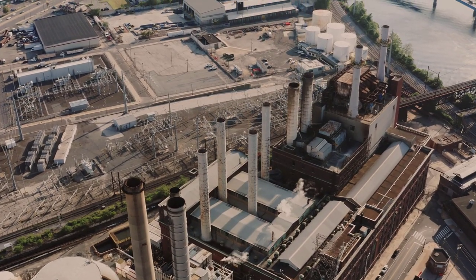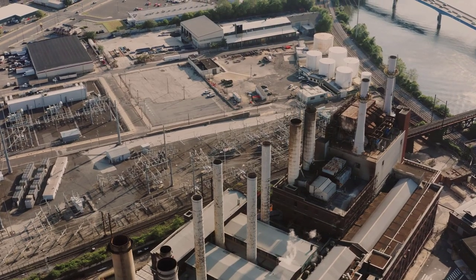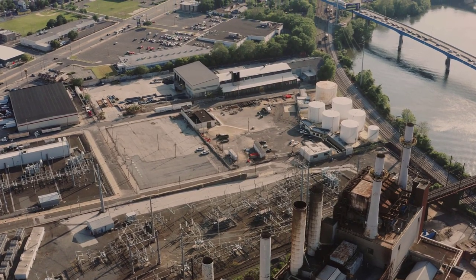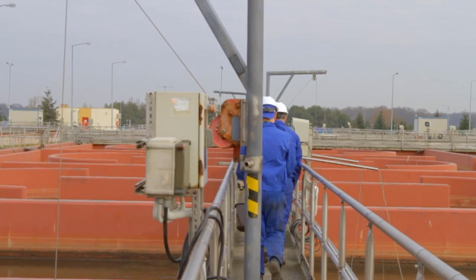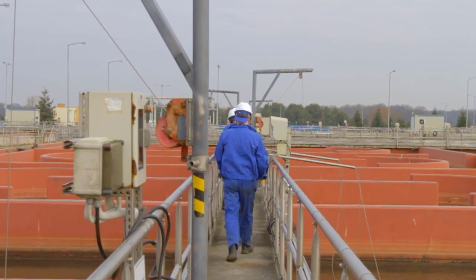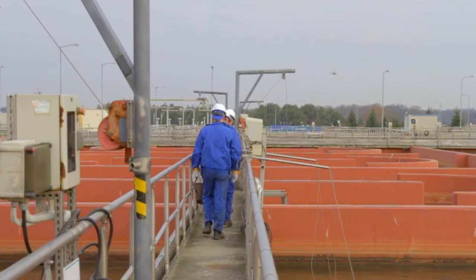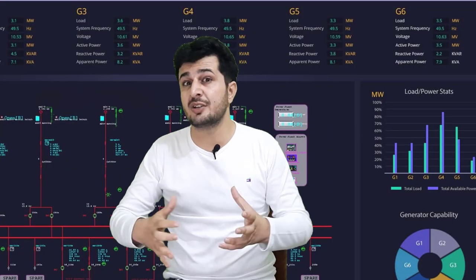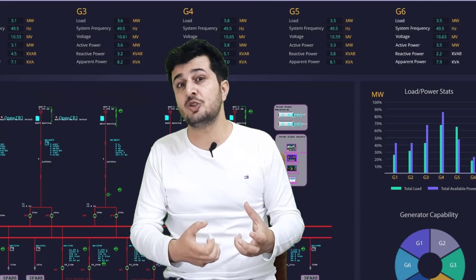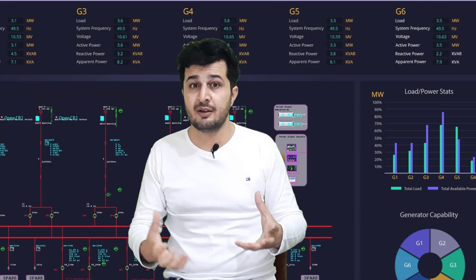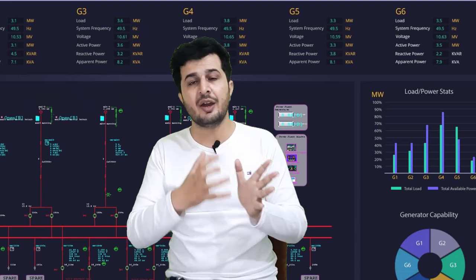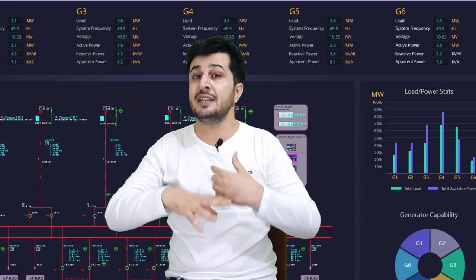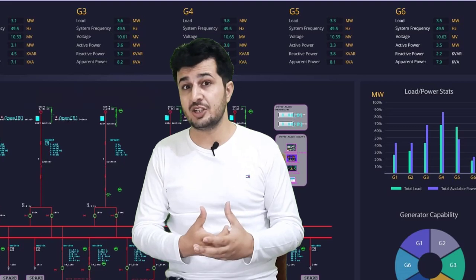SCADA transmits data and commands to PLCs and DCS systems to control a specified process. For example, a PLC would be used to control the flow of water through a part of an industrial process, and using a SCADA HMI system, the operator can vary the set point for the flow. Consider a wellhead located far away in a remote area with a harsh environment — to get important data from that wellhead, you would require an RTU sending data to a safe location through radio or another transmission medium.